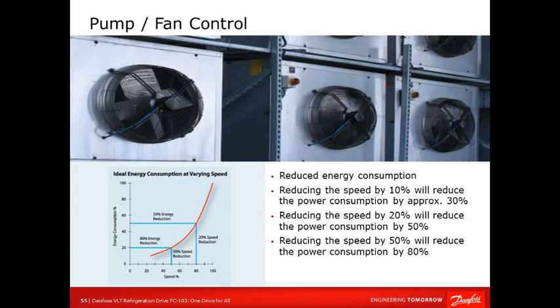For pump and fan control, obviously, why are customers applying this? If you're not familiar, there's an affinity law with utilizing a VFD for reducing speed, which affects the power consumption. This was just a quick overview to show, for example, that if you reduce the speed by 20%, you'll actually reduce the power consumption of the fans. And for condenser fan control, the advantage with this VFD is we can operate multiple fans in parallel, or obviously a single fan. We're monitoring the floating condensing temperature to adapt to the outdoor temperature, and obviously we're trying to improve the overall system COP, for example.